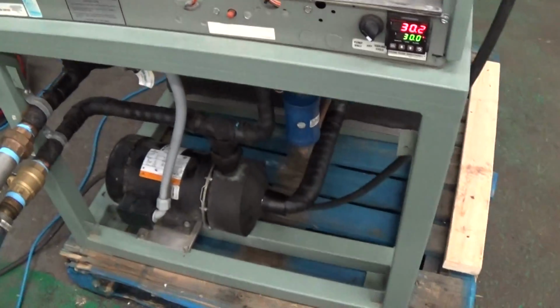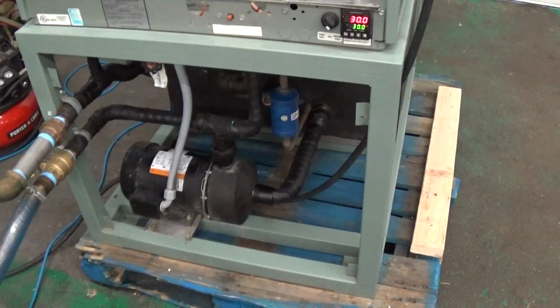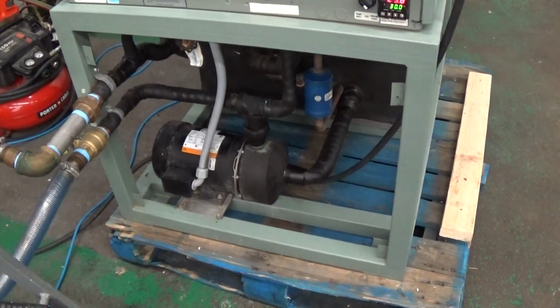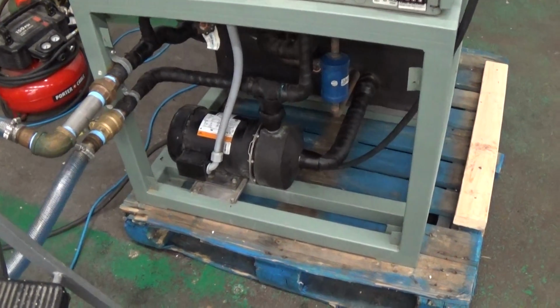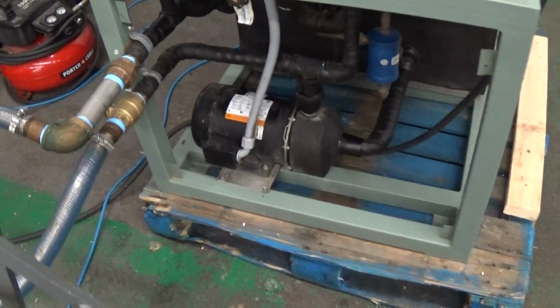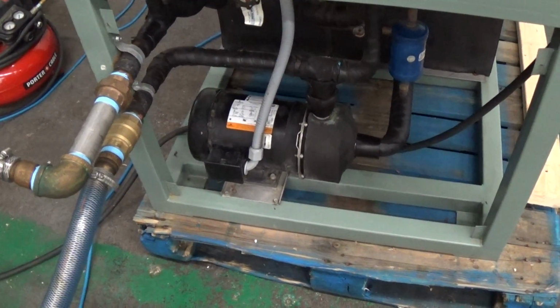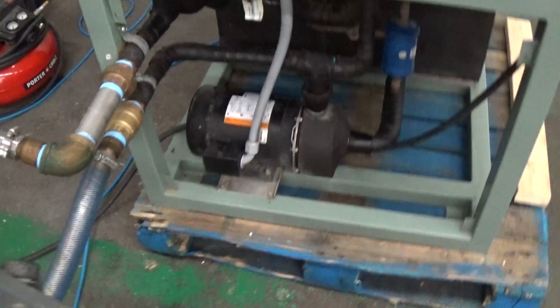When you do first start up the chiller, you can connect your three-phase power. It is three-phase, so it's rotation specific. In this case here, it's easy. You can look at the back of the pump and make sure you have correct rotation.